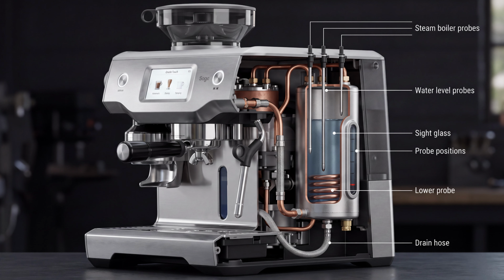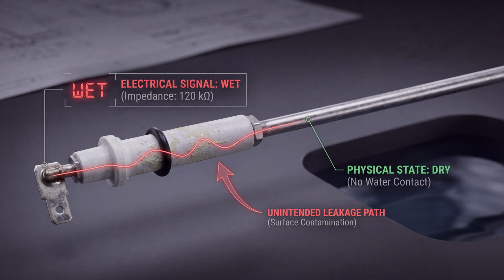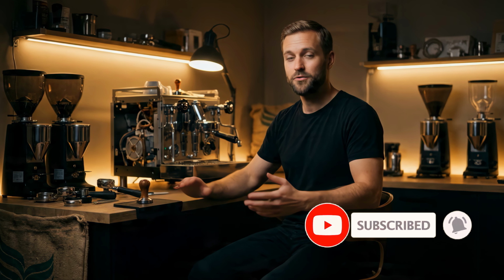And under normal use, you may never notice, because most of the time there really is water inside the boiler. The fault stays hidden. But then you descale the machine, and suddenly, that hidden fault matters. The boiler is drained. The water level falls below the probes. A healthy probe should change from wet to dry. The machine now knows the water is gone. But if an aging or contaminated probe continues to report wet, the physical reality and the electronic signal no longer agree. The boiler can be empty, while the machine believes there is still water inside. And during descaling, conductive liquid and residue around the probe can make that false signal even more significant.